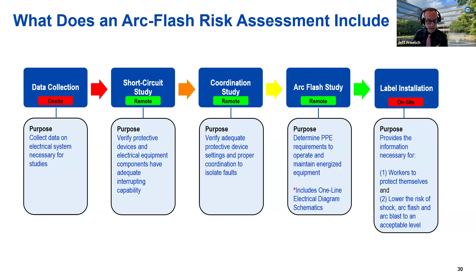Next slide. One of the underestimated elements of these studies is getting a single-line up-to-date drawing generated. The Arc Flash engineers will compile in their field assessments a configuration of the electrical system, as required under the standards of NFPA 70 and 70E. You want a clear, concise, efficient, and very thorough single-line diagram.